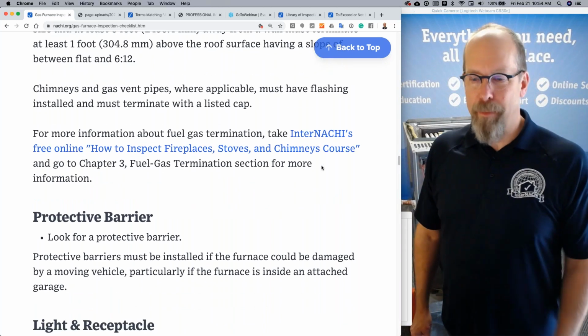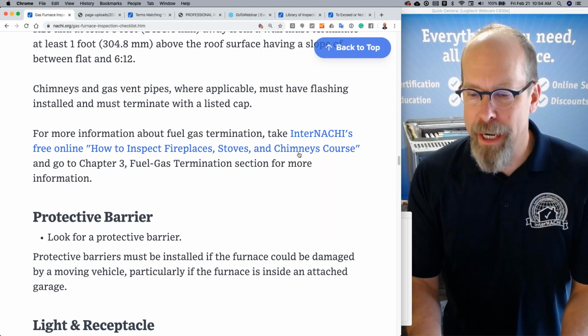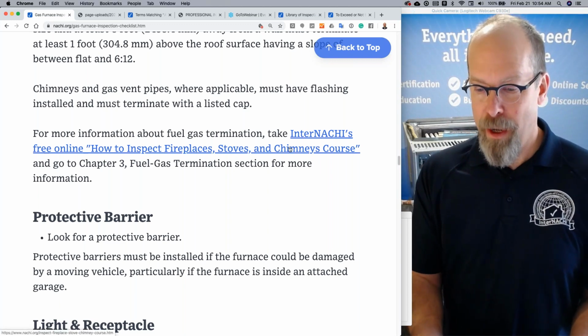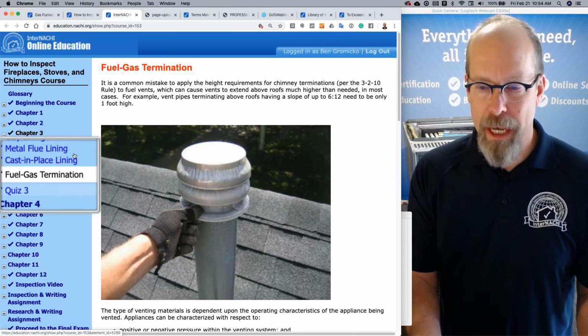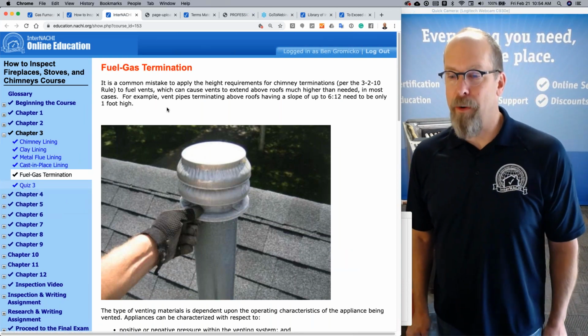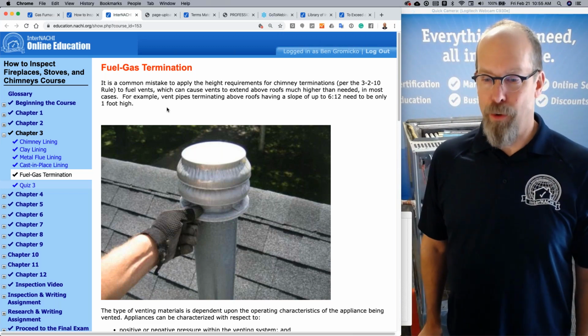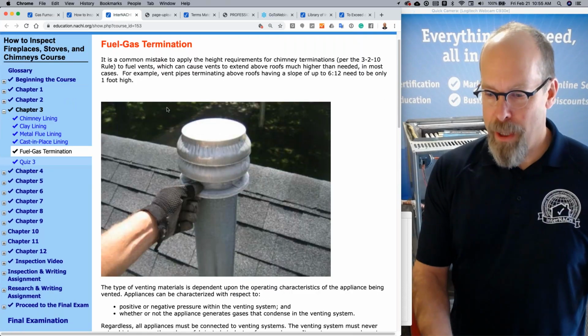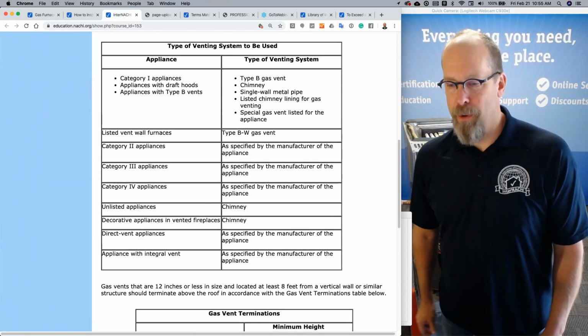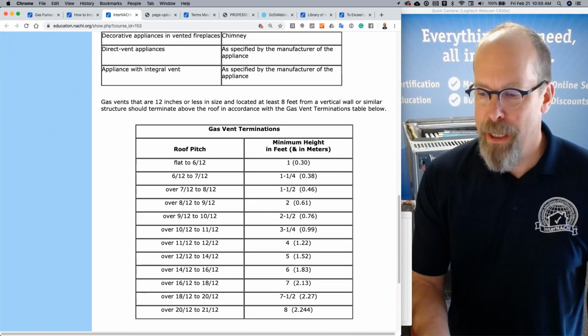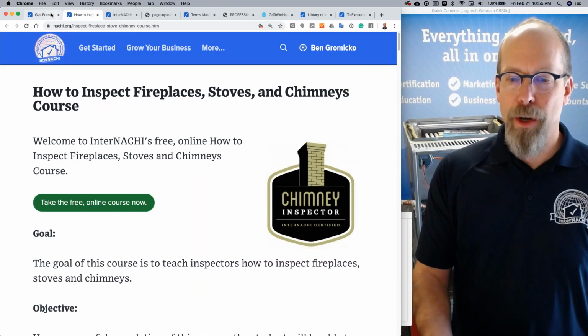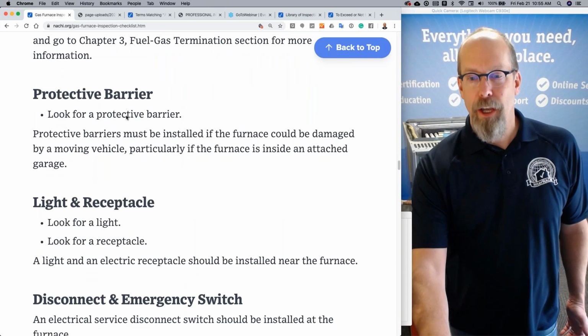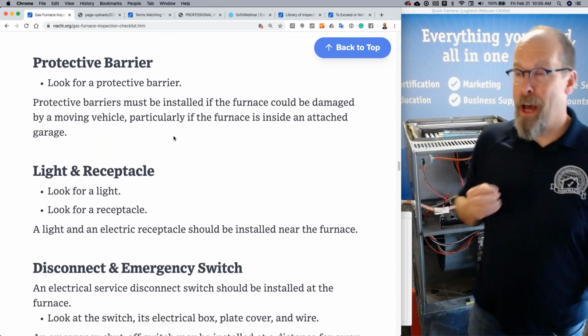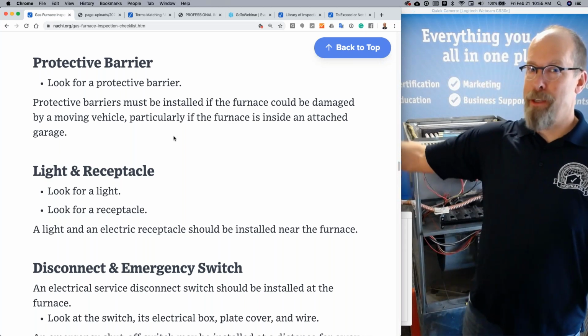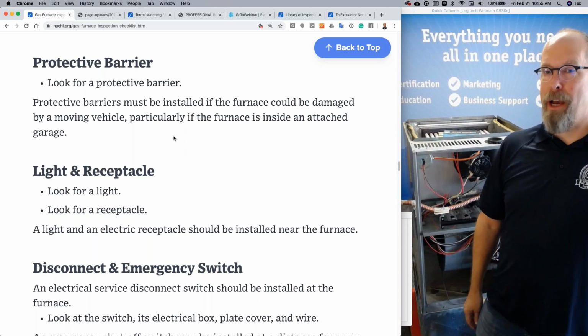Yep. For more information about fuel gas termination, take InterNACHI's free online How to Inspect Fireplaces, Stoves, and Chimneys course and go to Chapter 3, Fuel Gas Termination section. So let's go there. There it is. Oh, I got it right there. So there's fuel gas termination. It's a common mistake to apply the height requirements for chimney terminations per the 3-2-10 rule to fuel vents. So they're different. They're not the same, right? So there's the gas vent terminations. This is from standards, this is from code. We try to teach you what the rules are so that you don't look foolish up on a roof, applying one rule for masonry chimneys to the vent termination for this appliance behind me.